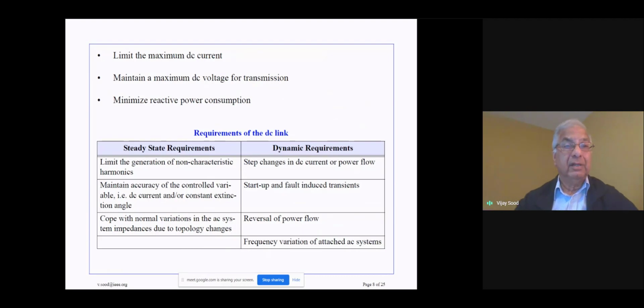The second requirement for the DC link is to maintain accuracy of the controlled variable, the DC current or the constant extinction angle. At the rectifier end, it's the DC current. At the inverter end, it's the extinction angle. And we want to make sure that those can be accurately controlled. Finally, we want to cope with normal variations in the AC system impedances due to any topology changes in the system. If there's any change in the topology of the interconnected AC systems feeding into the DC link, then there will be changes in the AC voltages. So we want to cope with those changes.